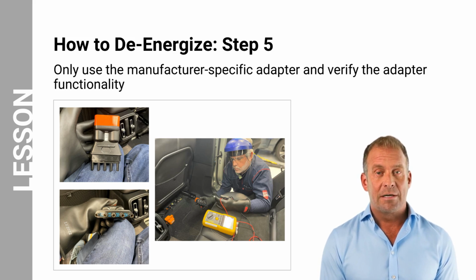Remember, a malfunctioning adapter could provide inaccurate readings, potentially compromising the reliability of your measurements. Verifying its functionality before and after de-energizing the high-voltage system ensures you have confidence in the test results and the overall safety of the process.